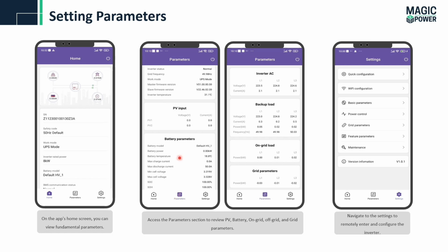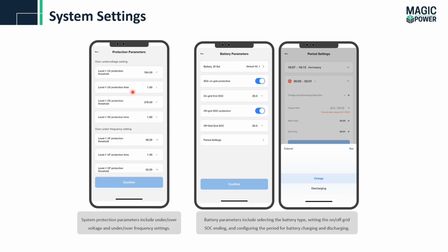Similarly, if you move to the parameters, we can see multiple parameters for the PV, battery, inverter, backup load, the grid side, and some grid parameters. In batteries, we can see the state of charge, state of health, voltage, current, and temperature. Next, moving to the settings, here you can see the quick configuration. It could be the operating mode of the system, some basic parameters, other power control, and maintenance. In maintenance, we can remotely control our system, turn it off, or restart it if required. Some other settings are for protection, for voltage protection, the minimum and maximum voltage.